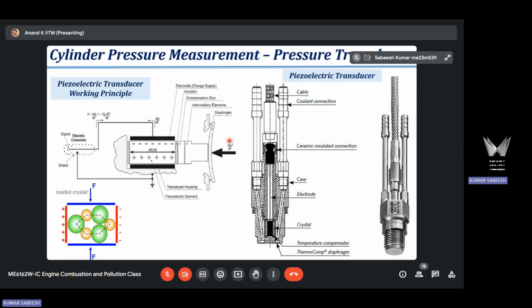Due to the rate of change of pressure, dp/dt, the diaphragm deflects and that is transmitted to the crystal. The crystal gets deformed at a rate of dε/dt. Once the crystal deforms, because of its property, it is charged. You can see that the opposite ends are oppositely charged, positive and negative. The compression of the crystal generates a charge. Here you have electrodes in contact with the crystal, and this effect is called the piezoelectric effect. Whenever a piezoelectric crystal is subjected to a strain, it generates electric charge. It's a property of this crystal. The electrodes in contact with the crystal carry this charge, dq/dt, to an external circuit. So this is where the pressure is applied. Because of the pressure inside the cylinder, the quartz crystal inside the sensor generates an electric charge, and the charge is carried away through this cable.